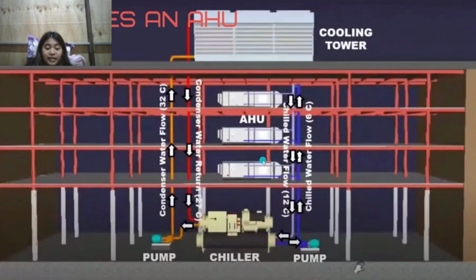To put it simply, there is a release of chilled water at around 6 degrees Celsius from the chiller to air handling units. Then there is a collection of warm water at around 12 degrees Celsius from the AHU going down to the chiller, up to the cooling tower to be released from the building.